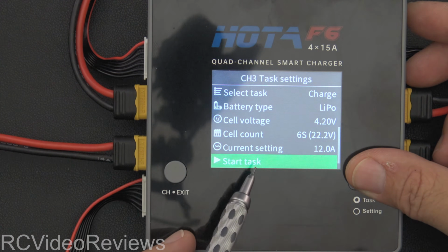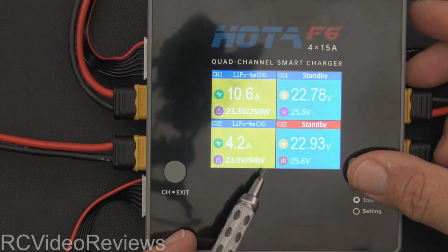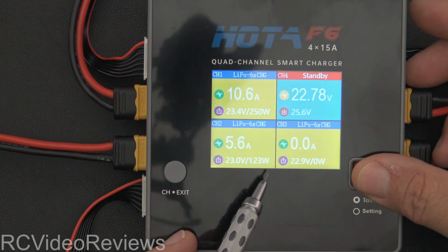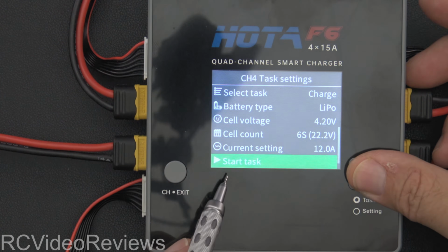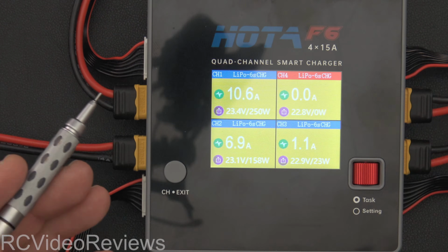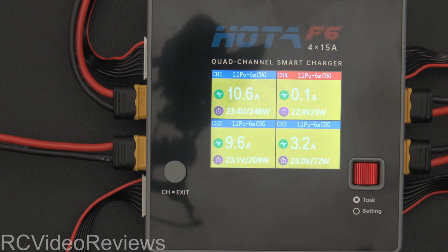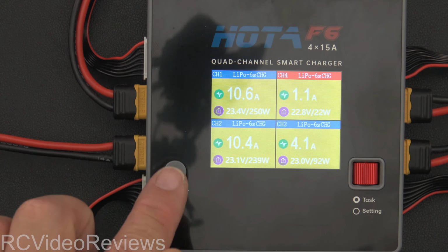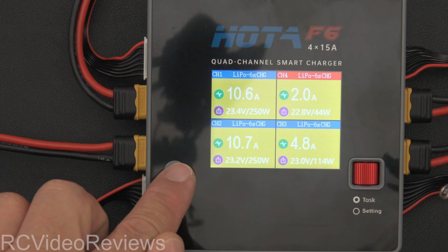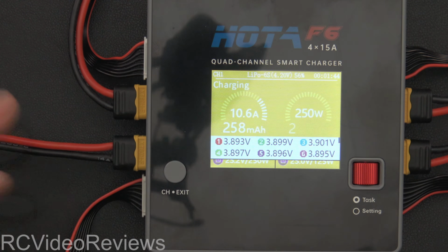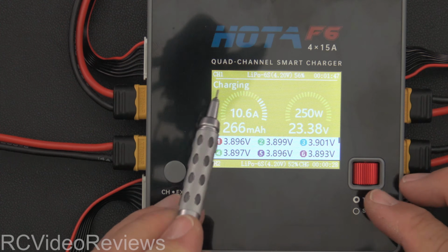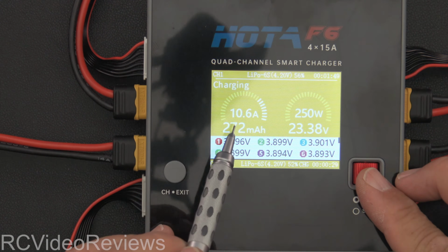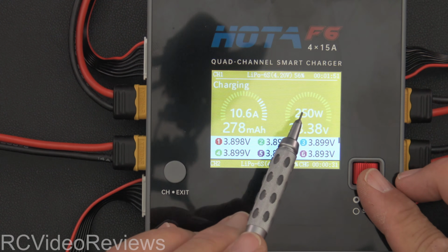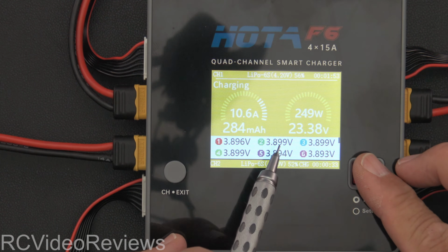Then we'll scroll over to number 3. There we go. There's number 3. What did I just say about skipping, right? And we'll hit start task, and then we'll go to number 4, and we'll do the same thing, start task. Now what we're looking for is for all of these to jump up to a full 250 watts. Now sometimes there's a button over here that lets you bring up the channels. So I'm going to click the button and that brings up the detail on the channel. So you can see now that we're on channel 1 and we're at 10.6 amps, 250 watts.